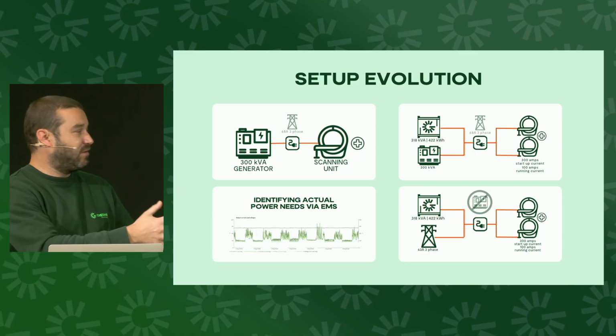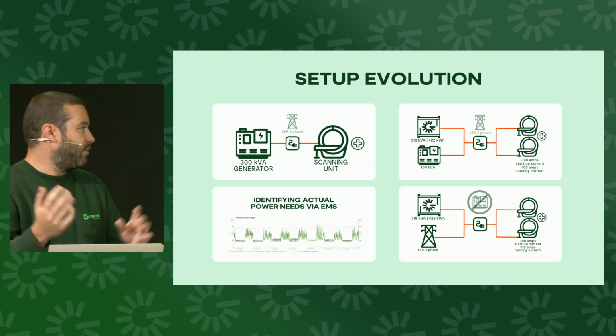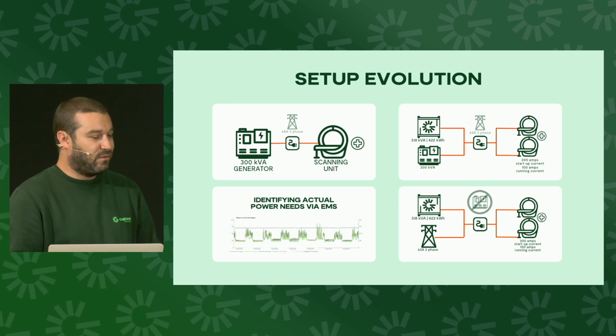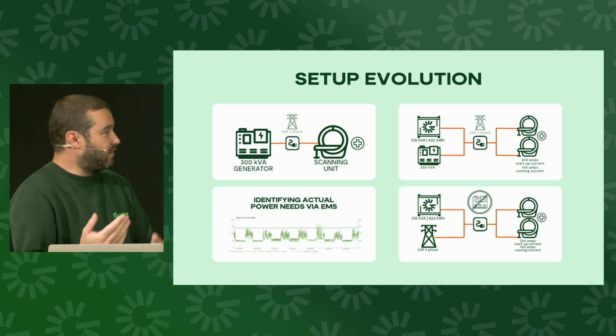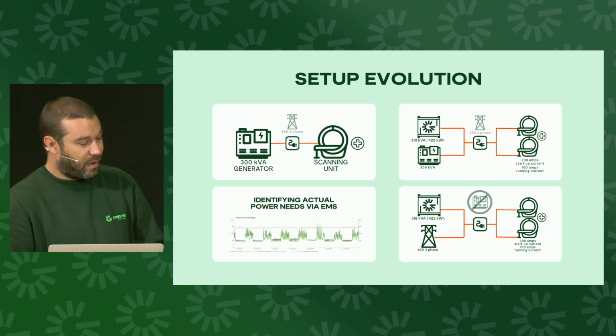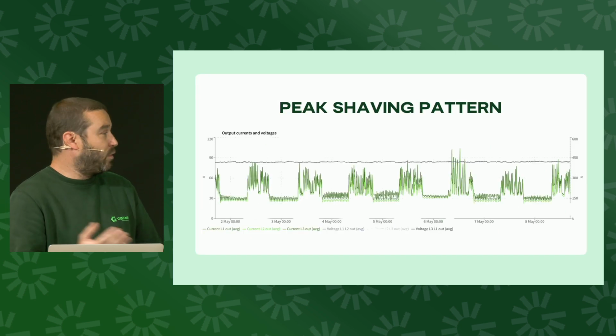It's often misunderstood quite how much physical energy you can harness from a very small grid connection, which again, most people just disregard these small grid connections because they think my load requires this, that's not going to do it. But by utilising the battery system, it really shows what you can do to drive these large bits of kit from very small power supplies. So that would be what we call peak shaving.